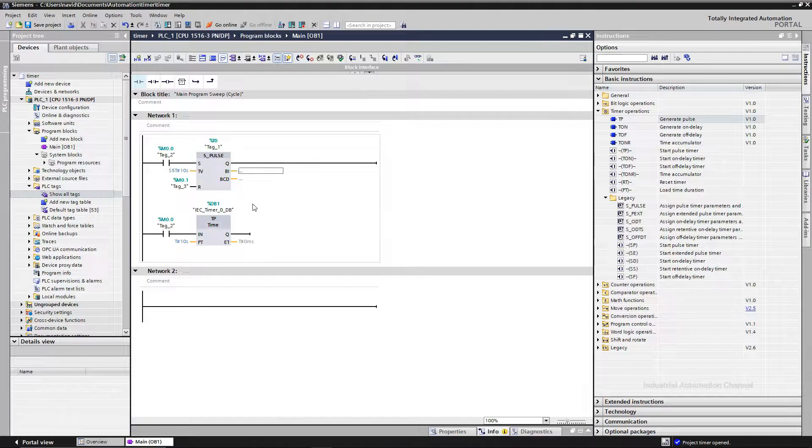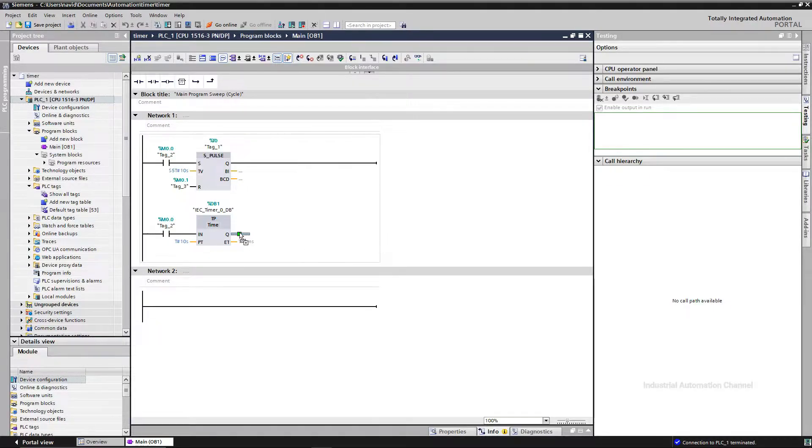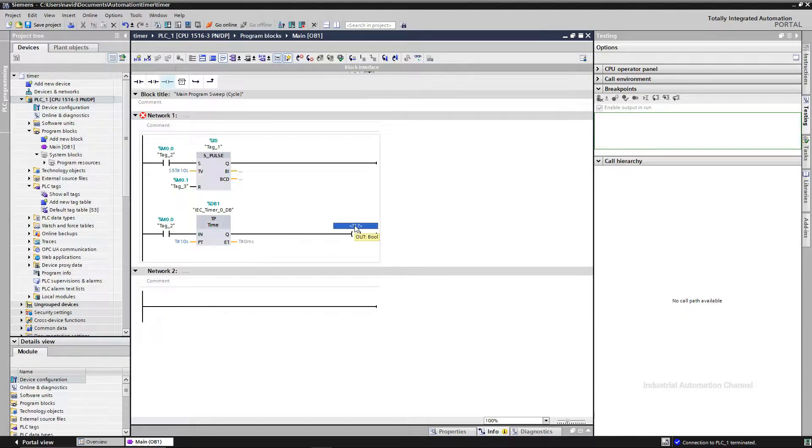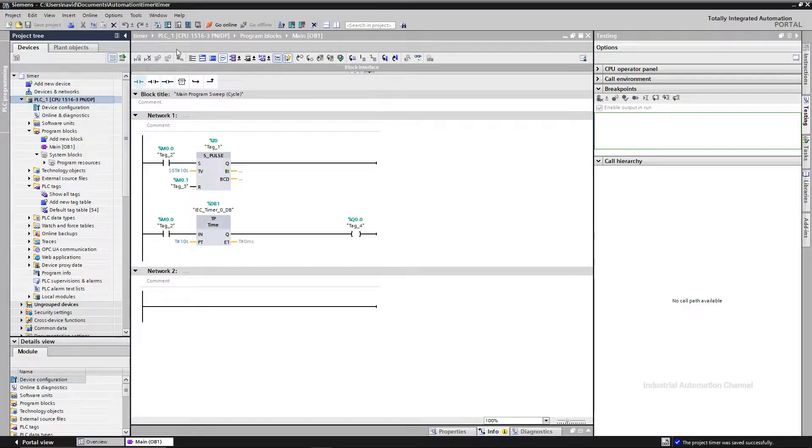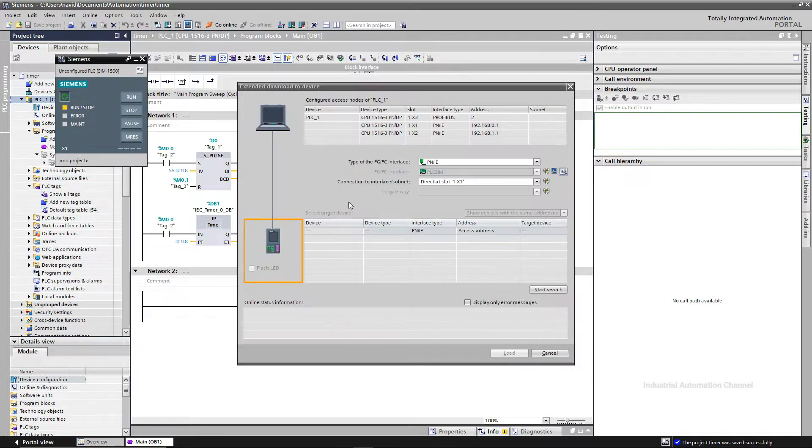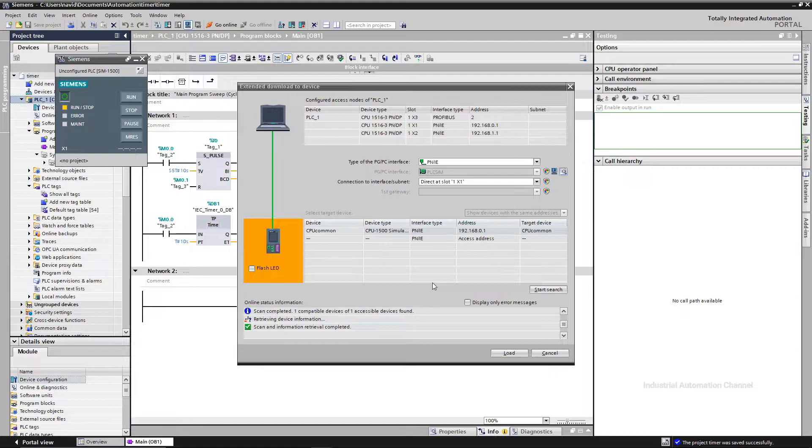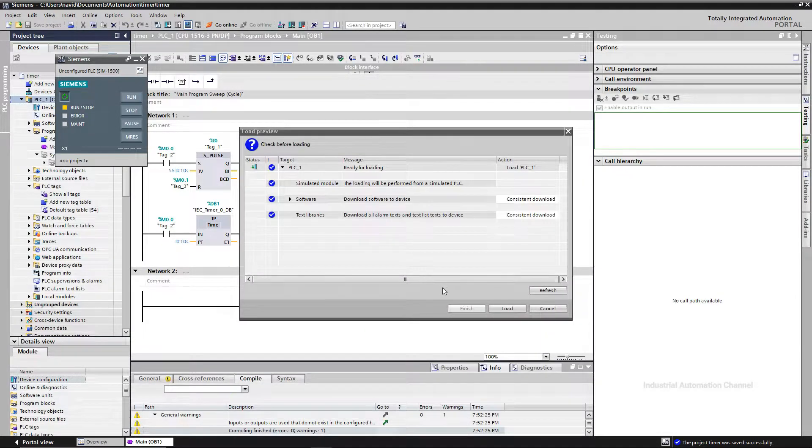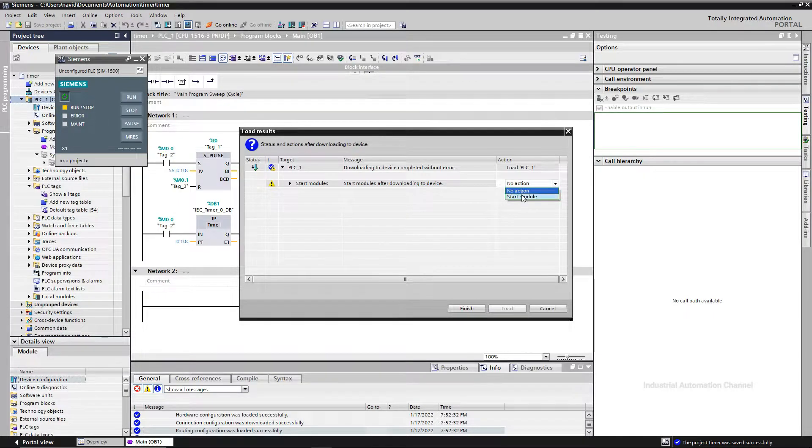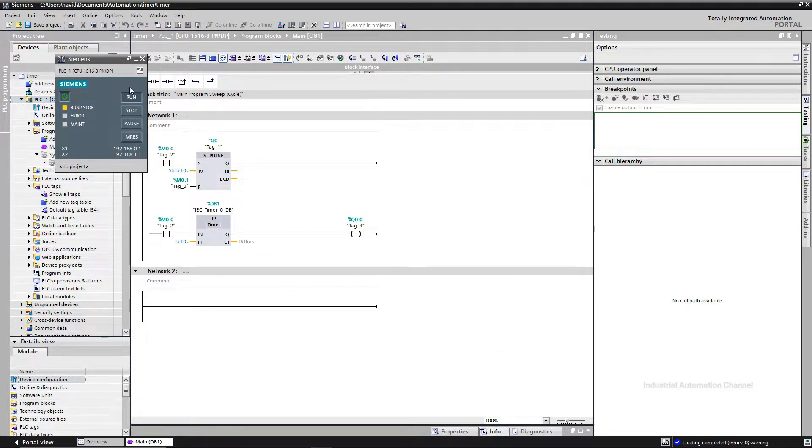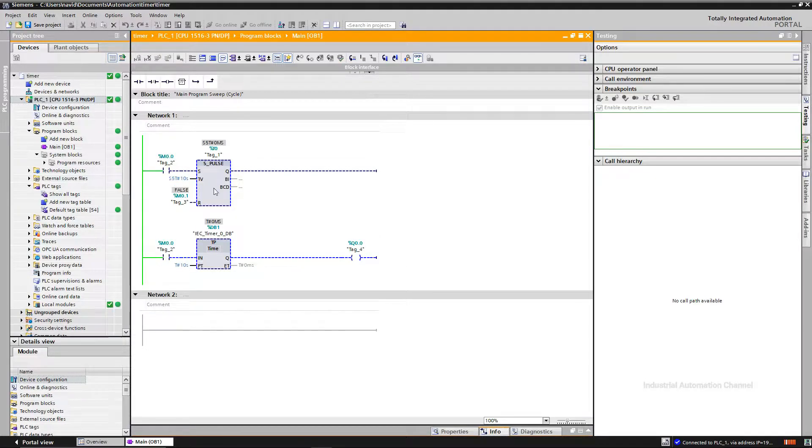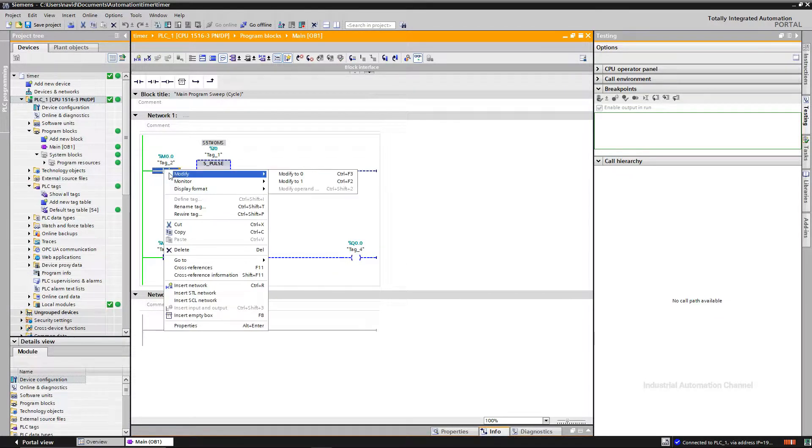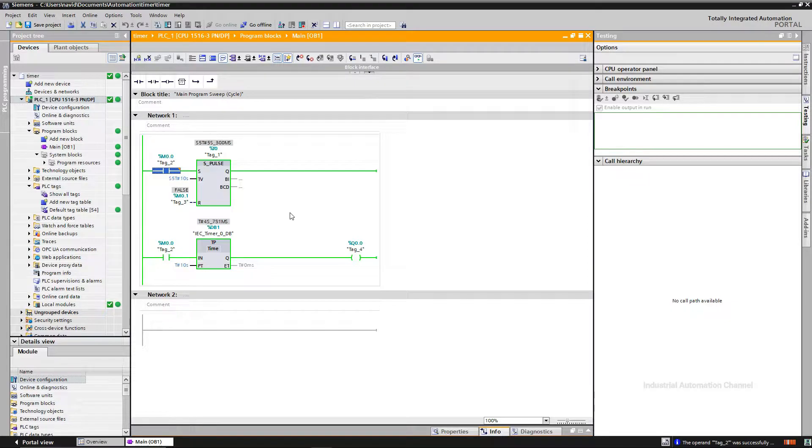BI and BCD outputs show the current time. BI shows it in binary format and BCD output is in BCD format. Let me download this timer and see how it works. I turn on the start input and output will be immediately on. When the timer is started, the time value will be counted down to zero. After this time, so after 10 seconds, the output will be turned off.